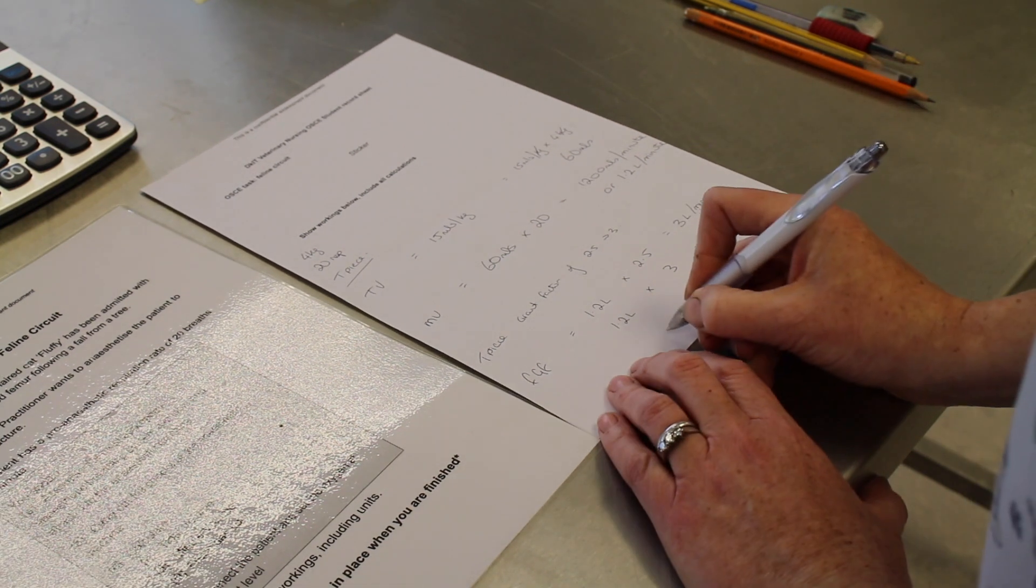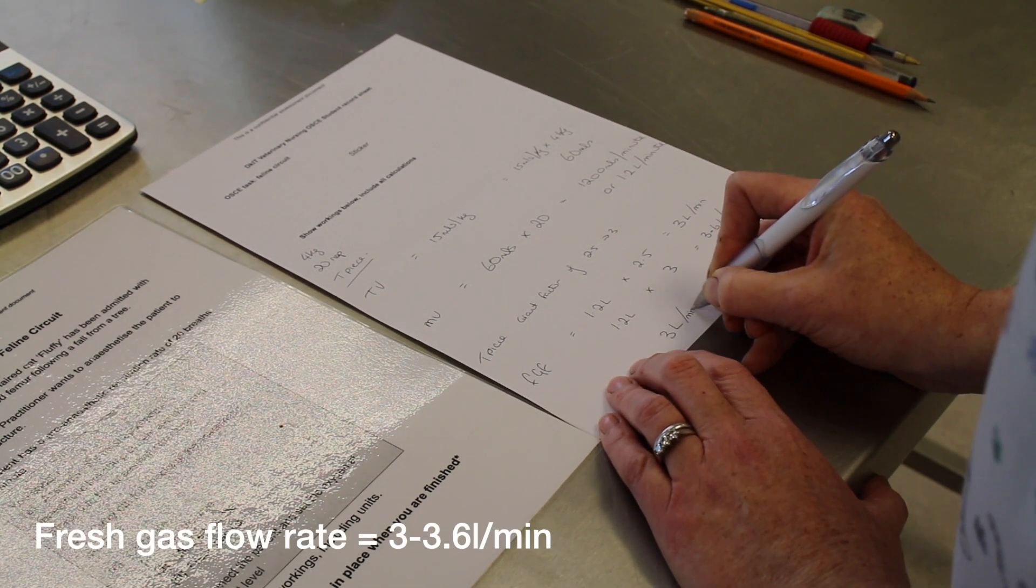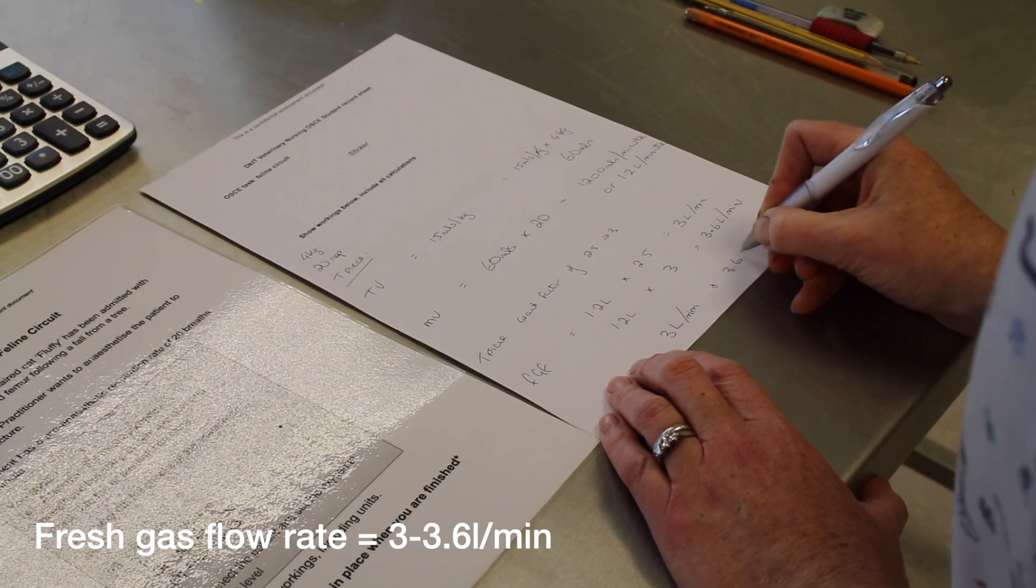So in this instance, we need to set our oxygen between 3 liters per minute and 3.6 liters per minute.